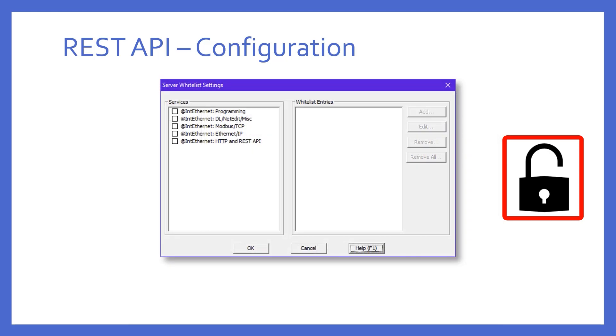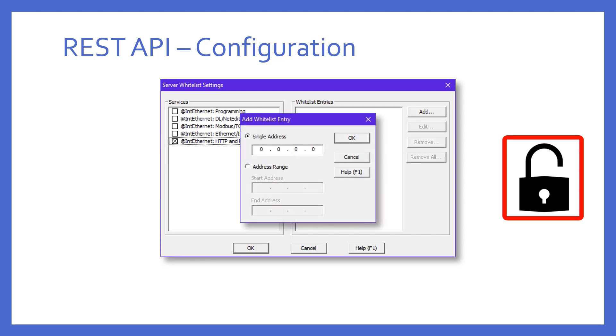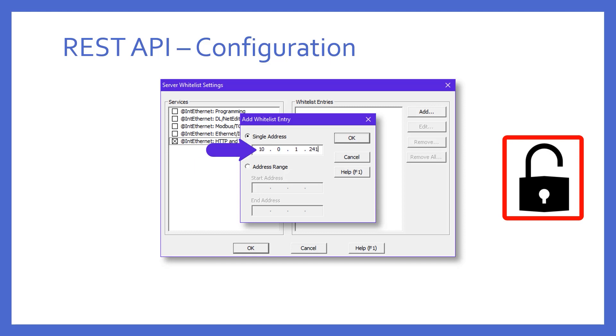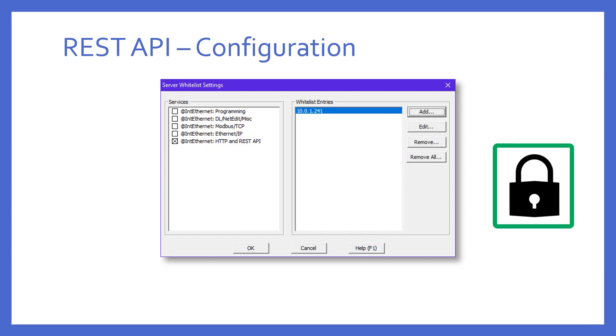There is a lot that we can say about this dialog, which we may cover in another video of its own. Suffice it to say briefly, the function of this Whitelist is to allow access to BRX PLC resources to certain IP addresses of the network that have been previously identified as safe. All other IP addresses will be rejected, but enabling this Whitelist doesn't really do anything unless you make some changes in this dialog. With regards to HTTP and REST API, if we put an X in the box, then you'll notice the Add button at the right is enabled. Then if you press the Add button, you can add IP addresses one at a time if they're non-contiguous or IP address ranges to the Whitelist. Here, I enter my PC's IP address, for example, and then I'd press the OK button. The result is this. This now means that the only IP address that can utilize the REST API is my particular PC in this case. All other IP addresses that attempt to utilize this service will be rejected.